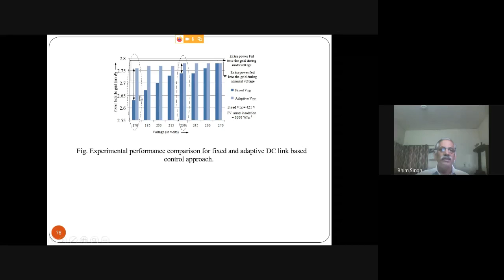In the case of a typically 2.5 kilowatt or 2.7 kilowatt system, we are able to push around 4% more generation to the grid, in spite of the losses of the boost converter. It means the loss reduction in the inverter has been much more than that, by taking this new concept where you have some voltage between the two. So that was the single phase.